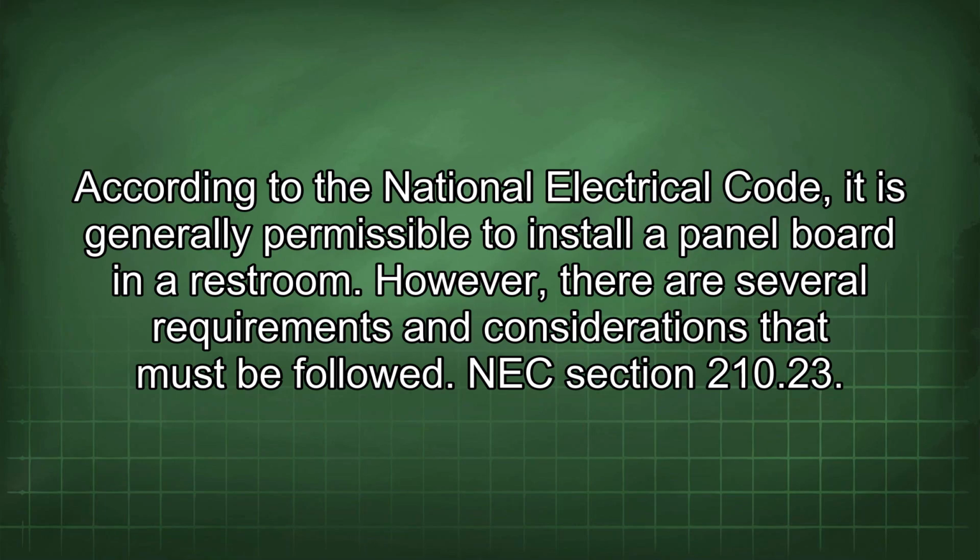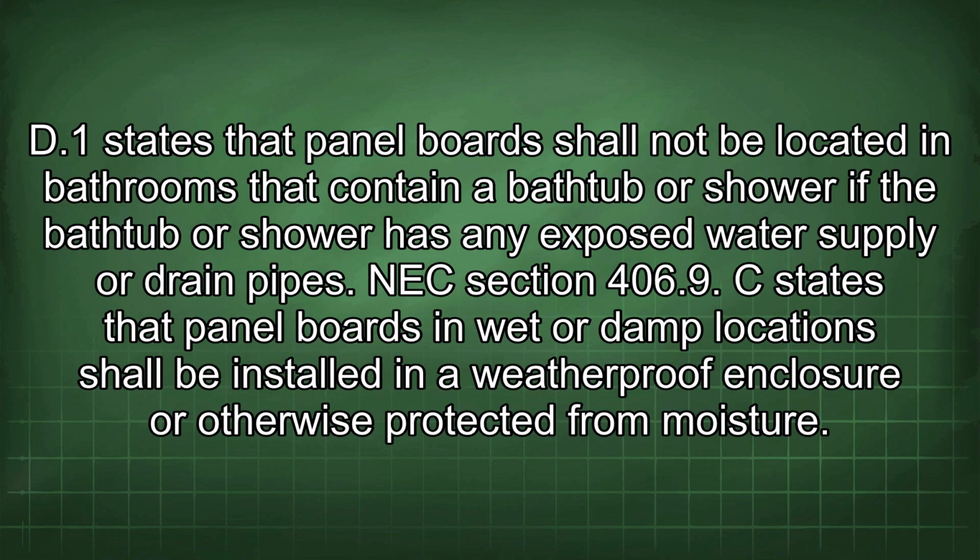According to the National Electrical Code, it is generally permissible to install a panel board in a restroom. However, there are several requirements and considerations that must be followed. NEC Section 210.23 D1 states that panel boards shall not be located in bathrooms that contain a bathtub or shower if the bathtub or shower has any exposed water supply or drain pipes.